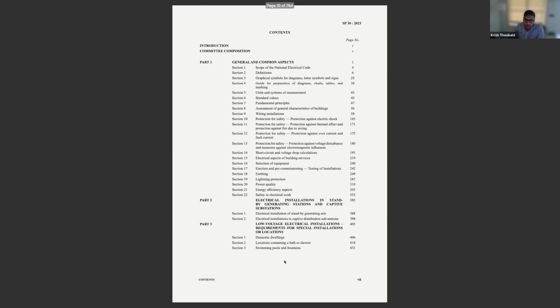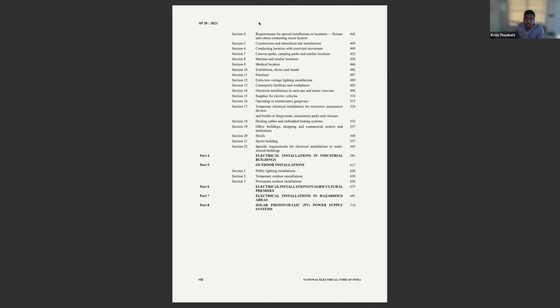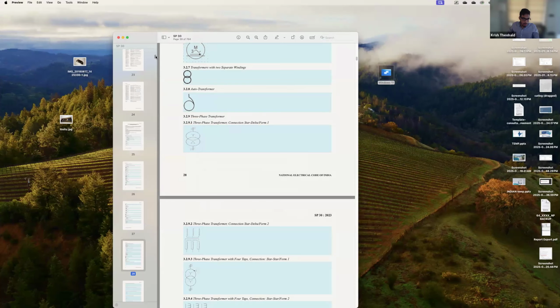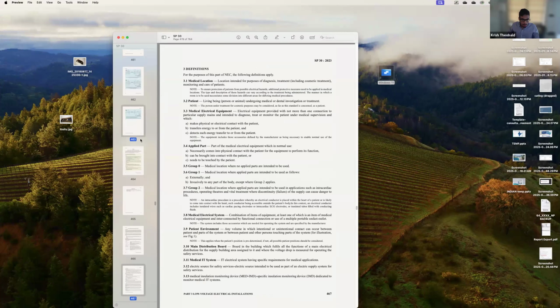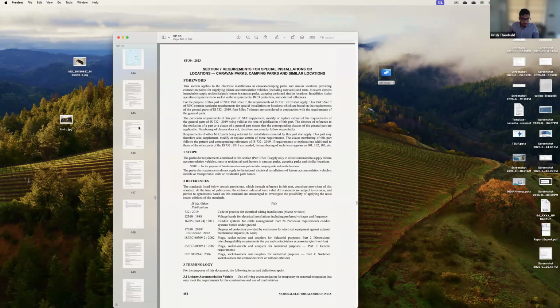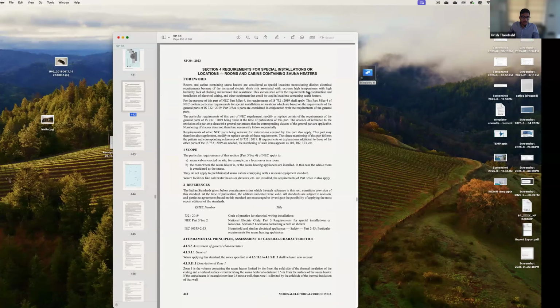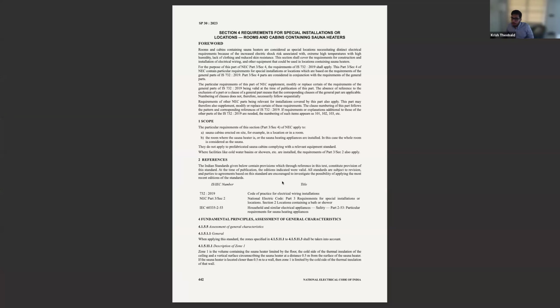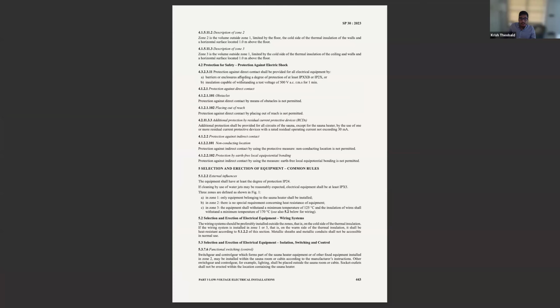Special locations. Here, requirements for special installations. Rooms and cabins containing sauna heaters is on page 442. So if I go to page 442, just a second. This provides requirements for sauna heaters. Now, these supplement and modify the general requirements of the standard. So, requirements for protection against electric shock, additional protection: here it says, additional protection shall be provided for all circuits of the sauna except the sauna heater by use of one or more residual current protective devices.